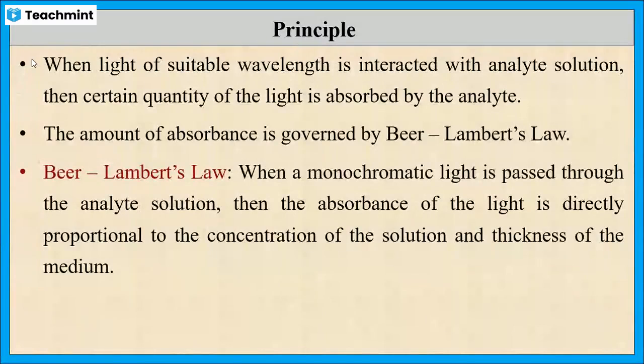Now let us see the principle of colorimetry. When a light of suitable wavelength is interacted with the sample solution, a certain quantity of the light is absorbed by the colored sample. The quantity of absorption is governed by Beer-Lambert's law. According to this law, when monochromatic light is passed through the analyte solution, the absorbance of light is directly proportional to the concentration of the solution and the thickness of the medium.